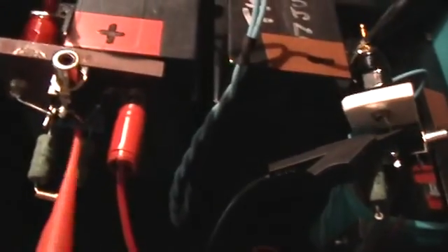Now we're going through that shunt, and I can take the Fluke oscilloscope probe and just hook the positive lead of the probe to the more positive side of the shunt, and the ground on the other side. Now the Fluke is completely floating.